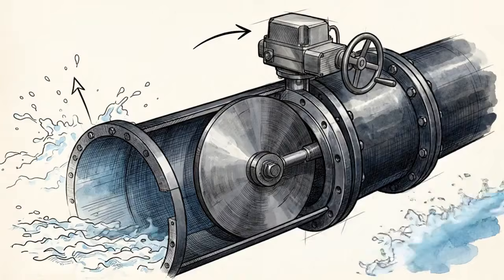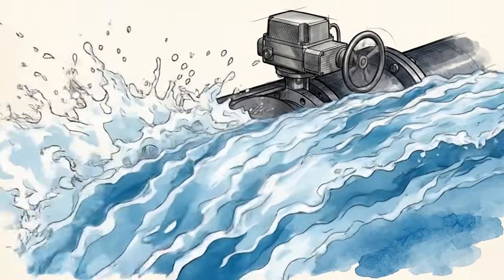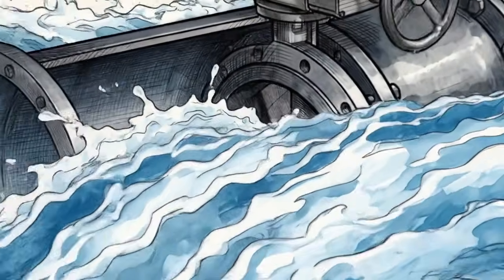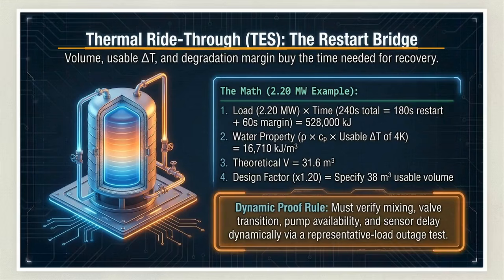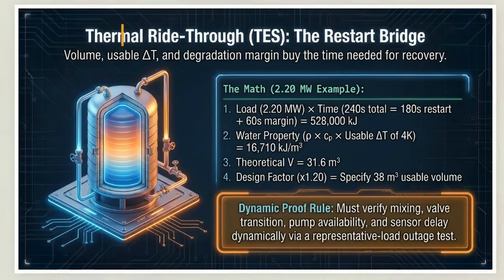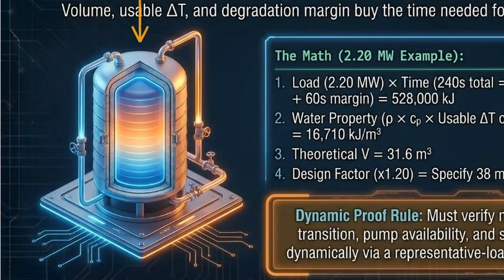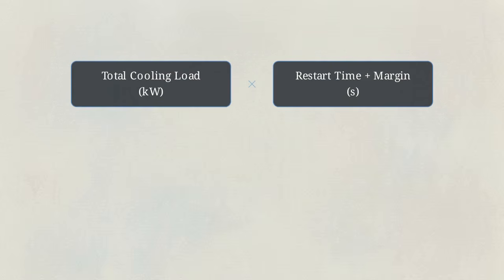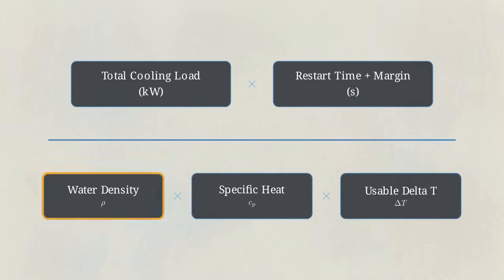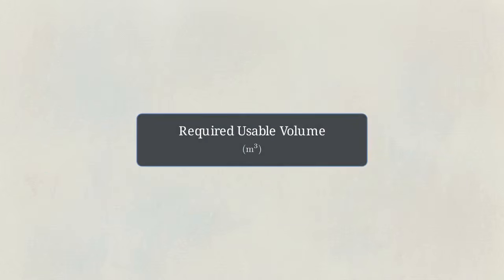Thousands of gallons of water must forcefully surge through the industrial pipes. This graphic breaks down the thermal ride-through. While the chillers are offline and the pumps are spinning up, a thermal energy storage tank, or TES, actively absorbs the IT heat load to bridge the gap. Sizing this tank requires exact mathematics, multiplying the total cooling load by the time required for restart, and dividing that by the product of water density, specific heat, and the usable delta T.